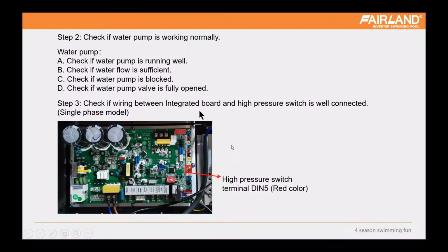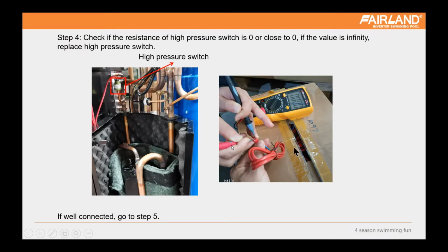And if the E1 here, I suggest E1 normally happens after the compressor is running, and only after that it will cause high pressure and trigger the high pressure protection. But sometimes when you power on the unit, you will find that before the compressor runs, there's also an E1. That's a hardware problem, like the wire, the integrated board, or even the high pressure switch. So we will have a detection. The detection on our part is not much, but one of them is the high pressure switch. You can detect whether the high pressure switch is normal or not. If normal, the value is zero; if not, it's infinite. So you can do a simple detection to make sure the high pressure switch is fine.